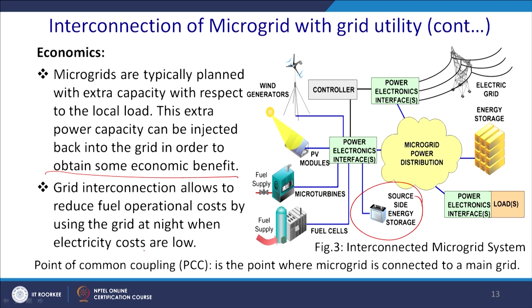Power electronics interfaces. So, now we have a solar inverter and islanding techniques, all of those placed, and they have static switches mostly for maintenance purposes, and directly through the circuit breakers you can also do that. Relatively simple and inexpensive, but it requires cycles of operation, a slow 2 to 3 cycles to achieve complete disconnection. Since electrical characteristics on both sides of the circuit breaker must be the same, the electrical characteristics on the microgrid side are dependent on the grid side characteristics.